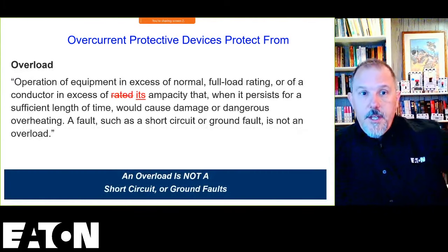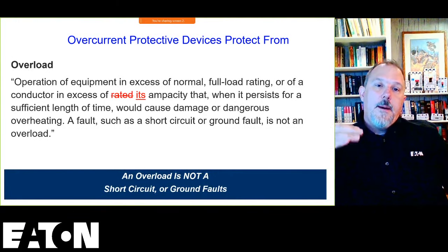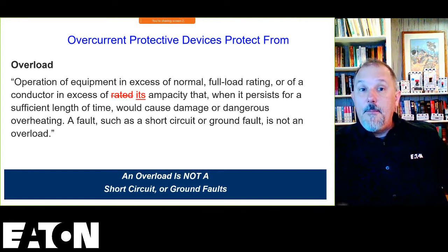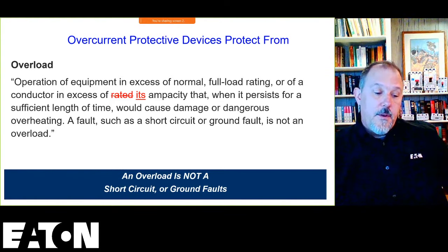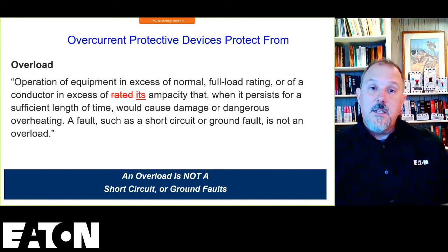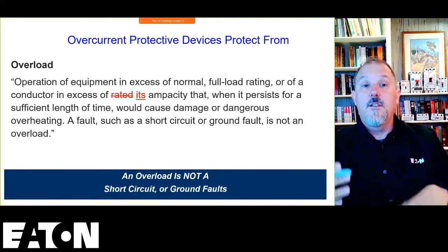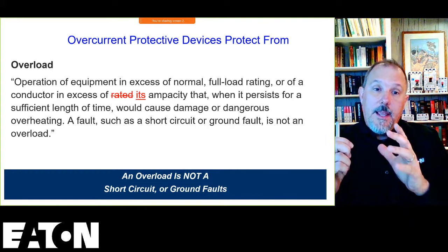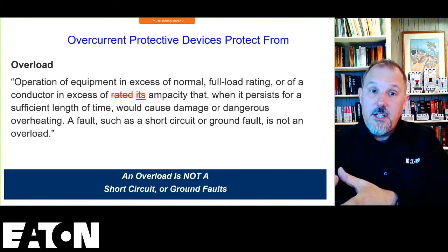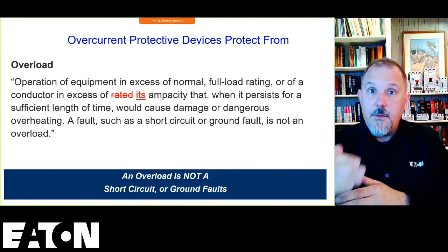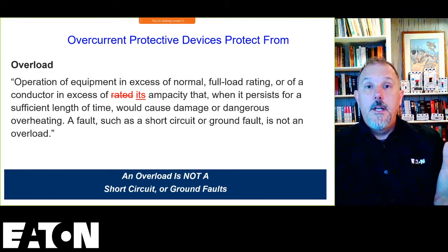So an overload is operating in excess of its normal full load rating, or of a conductor in excess of its ampacity. And we just changed that. We removed the word "rated" from the 2020 code as part of a task group that I chaired, because rated ampacity doesn't have a place. Ampacity is all based on conditions of use. So when I exceed the ampacity, which is based upon the conditions of use, I'm in an overload condition.